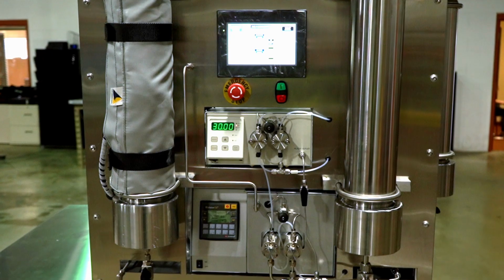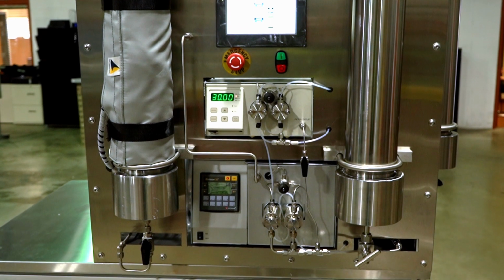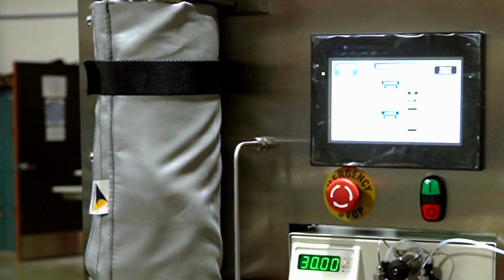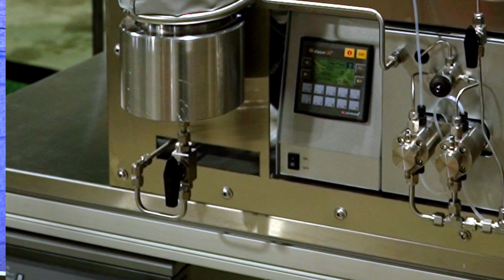So overall, just to describe the unit, it's a system typically comprised of two pumps, one being a solvent gradient and the other being a CO2 pump. The CO2 pump provides CO2 to the extractor column. The extractor column is 2.5 liters typically. And after the extractor column, you'd have a back pressure regulator. The back pressure regulator is manual.